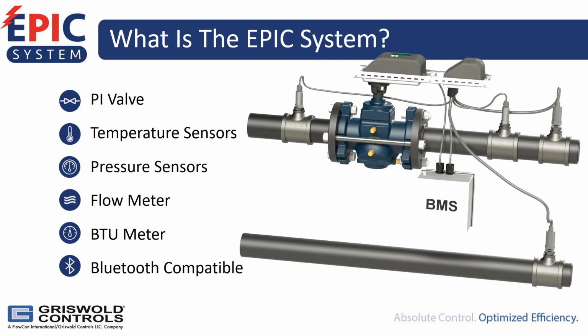Included also in the EPIC system are the temperature sensors. And because we're measuring the temperature across some piece of heat transfer equipment, whether it's an air handling unit or a coil, there's a temperature sensor on both the inlet and outlet of the coil so that we can be constantly monitoring the delta T across the heat transfer equipment.